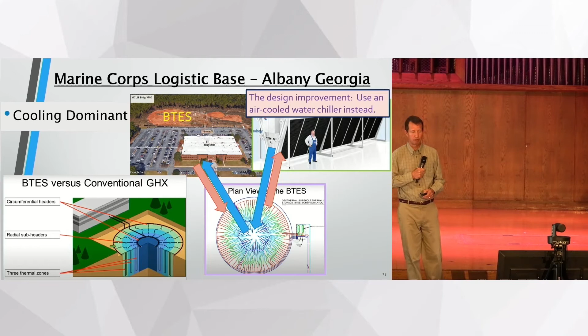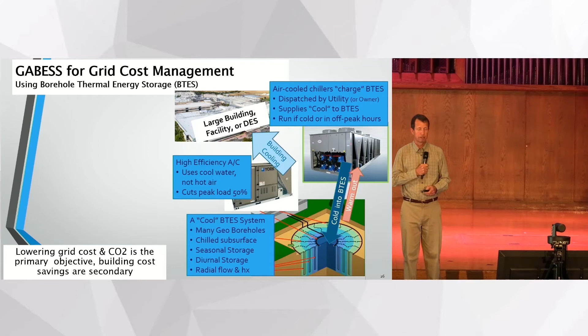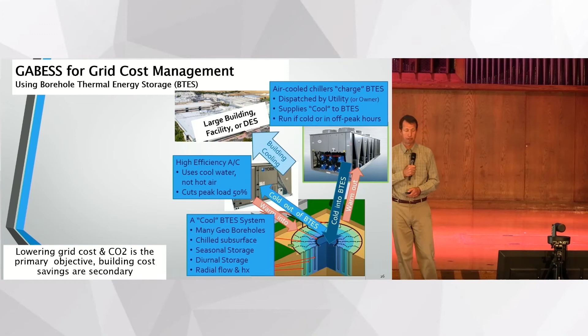We'll start out looking at a cold weather, cooling application first. Here's an air source chiller. It's going to provide cold into this BTES, and then a water source heat pump, a geothermal heat pump, is going to pull heat out of the building or buildings, if it's a district energy system, and put that heat back into the water. So cold into the center to charge the BTES, and cold out of the center to supply the district energy system.